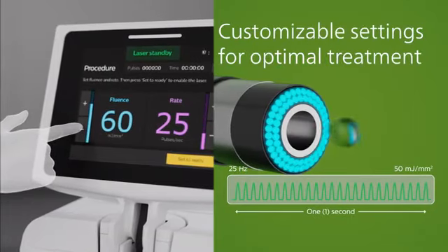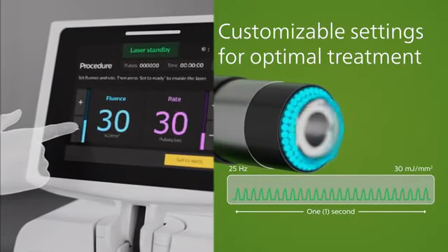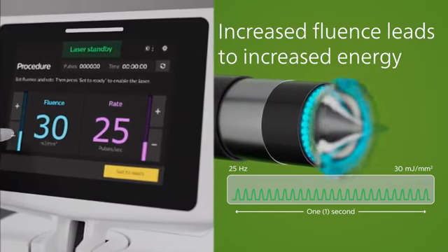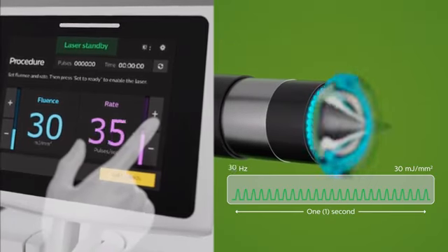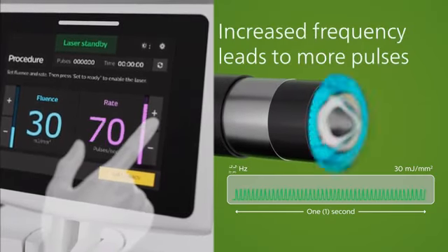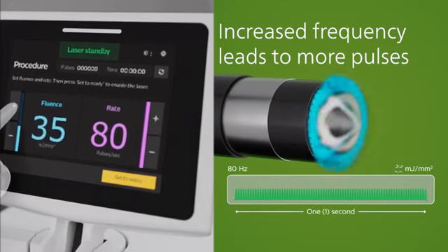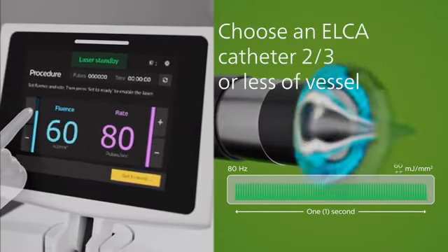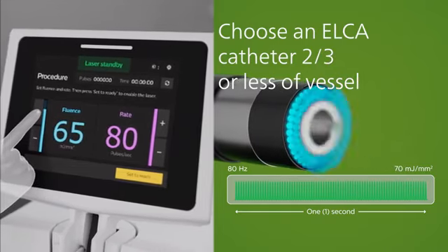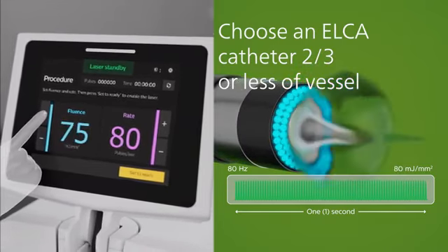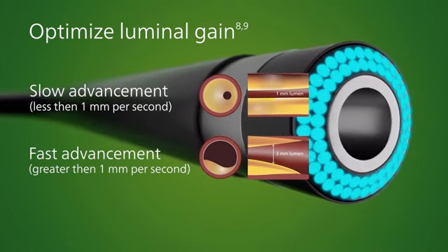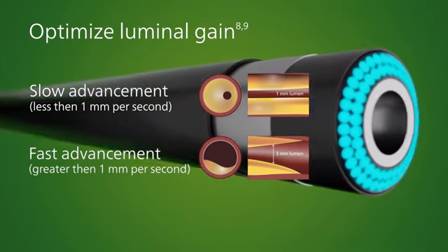ELCA has customizable energy and frequency modes to effectively debulk different morphologies. Fluence is the energy that is created during photoablation. Rate is the number of times per second the three mechanisms of action occur during photoablation. At max fluence settings, the cavitation bubble will be approximately 50% larger than the tip of the catheter, maximizing debulking. With slow and repeated advancements of ELCA, you can optimize your luminal gain.